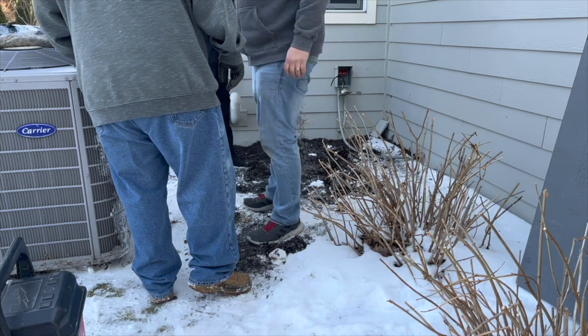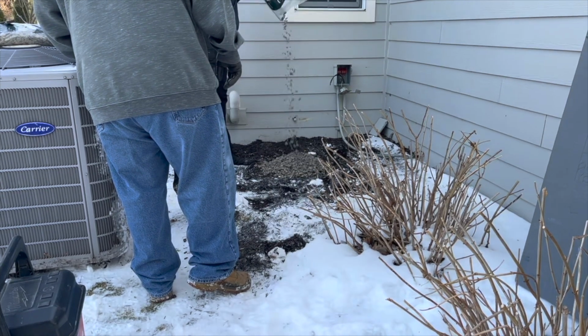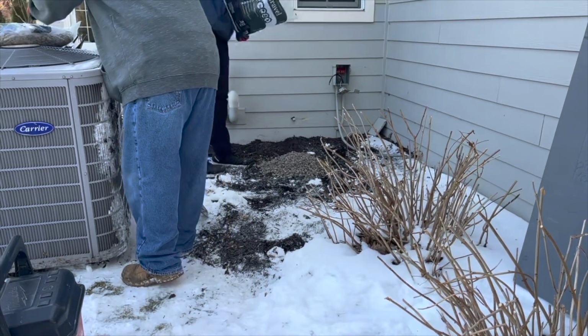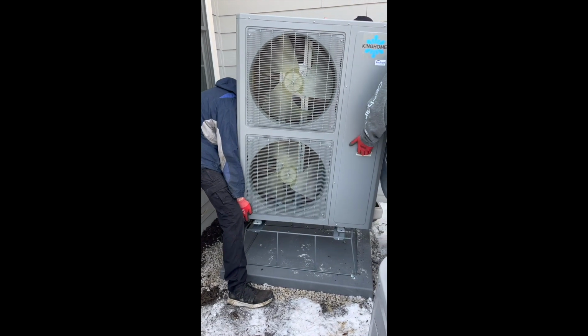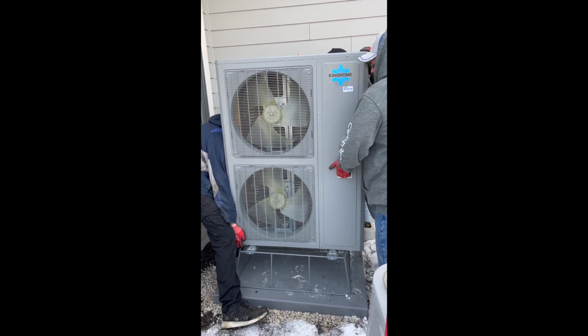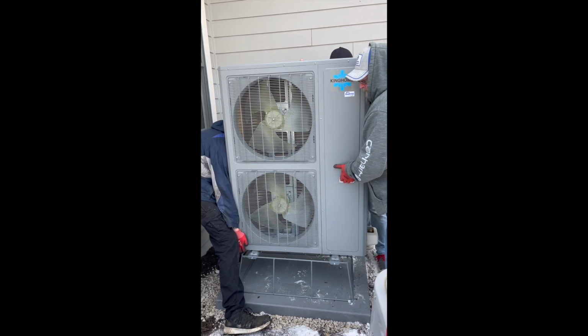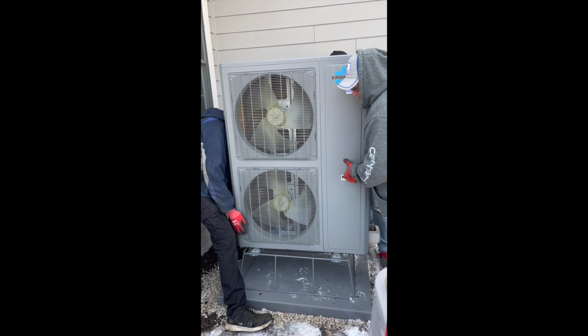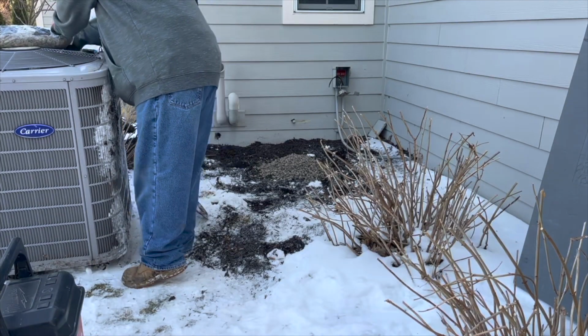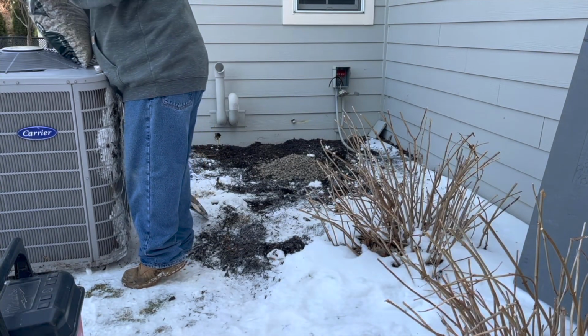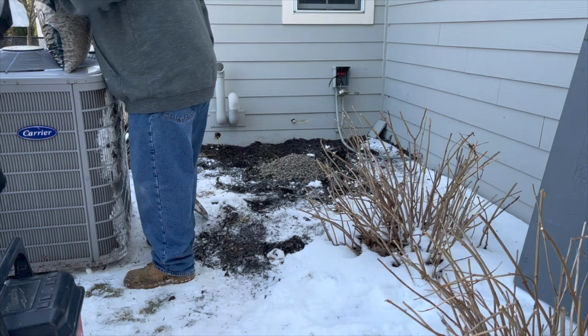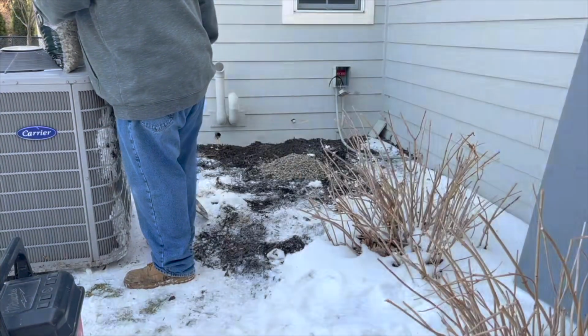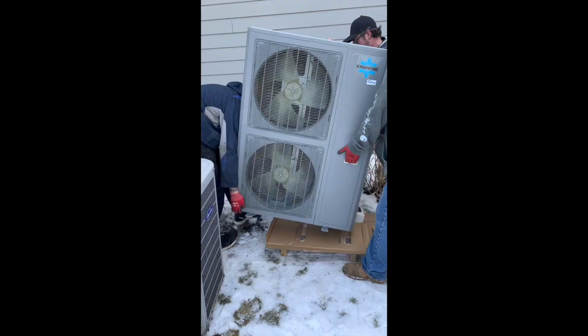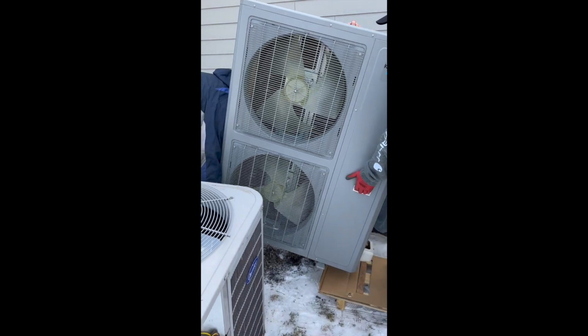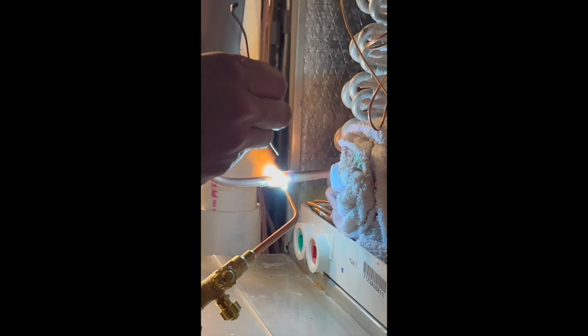Now we're going to set the outdoor unit. First of all, let's just remember for a heat pump, it's not a condensing unit, it's an outdoor unit. Let's get those designations correct, people. The heat pump needs to be raised up on a stand. That's because in winter, ice will form on the condenser coils. Fear not, the unit has a built-in defrost cycle. When the water drips off, we don't want the unit sitting in an ice bath. The contractor will lay some gravel on the ground first, then put on the pad and then the stand. You can see that it takes a couple of tough hombres to get this installed.